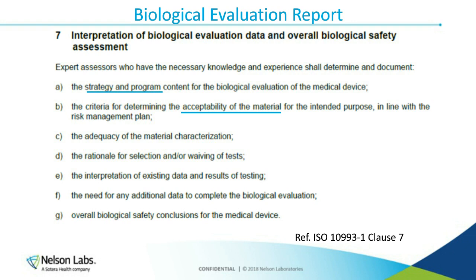Your strategy for the program really comes from your initial risk assessment. Are you looking at the appropriate risks of the device? That needs to be addressed again in your summary report as another justification. The way I like to think about this biological evaluation report is that it's the conclusion in your story. We want to have a good ending, and in that conclusion we're summarizing everything that's happened. We do need to state our beginning place of thought because that ties into the end, where we're saying that what we did was appropriate.